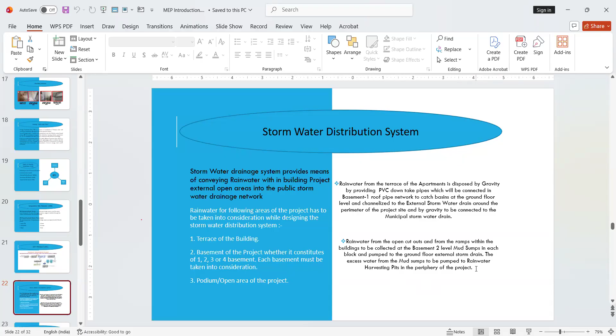Now coming to rainwater from the open cutouts and the ramp — this goes to the basement 2 level. Basement 2 can have a mud sump with a lifting pump. Again, from basement 2, 3, 4, whatever, it is pumped to the ground floor external stormwater drain, and the excess water from the mud sumps is pumped to the rainwater harvesting pit in the periphery of the project. I will tell you about the rainwater harvesting pit.